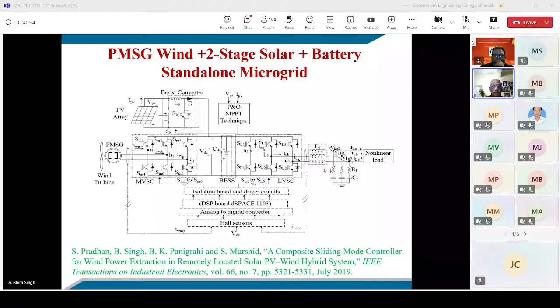If we put a straight line from 12 meters per second, you'll find you're not able to generate much power typically at lower wind speed. But if you look at 7.2 meters per second, you hardly have zero generation. However, if you go to variable speed and reduce the turbine speed to 60%, you're able to get 20% generation.